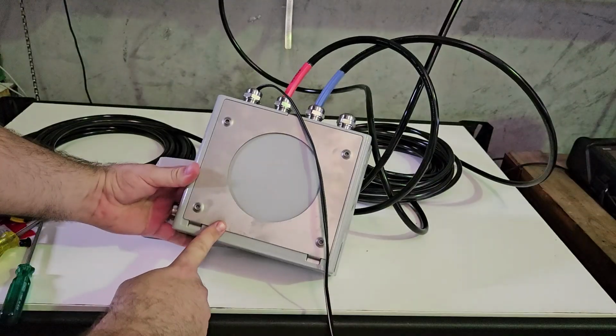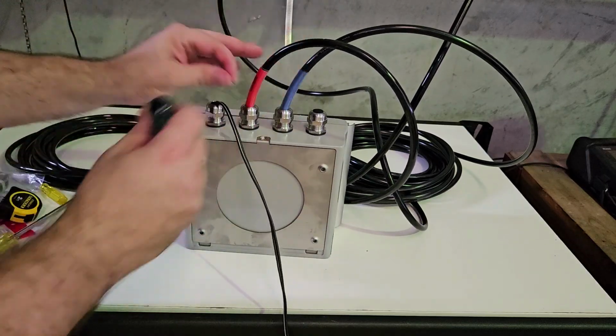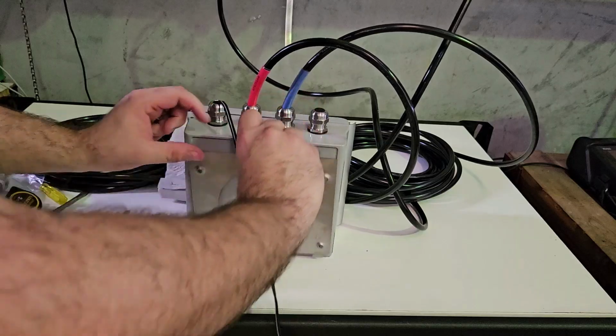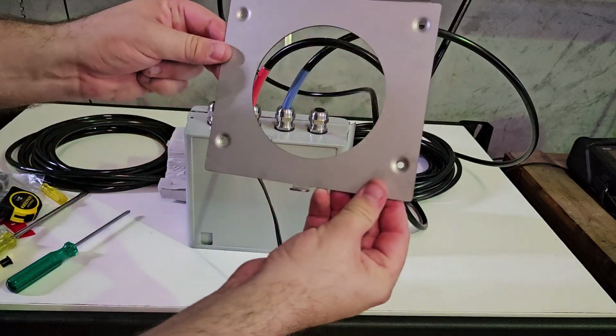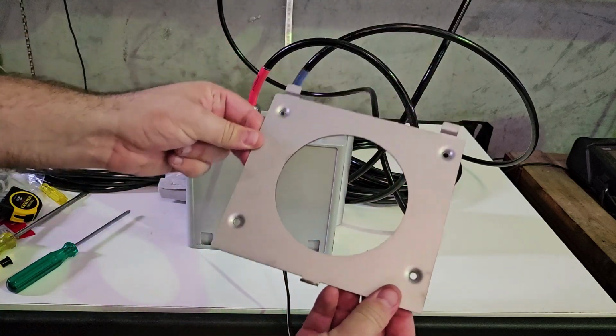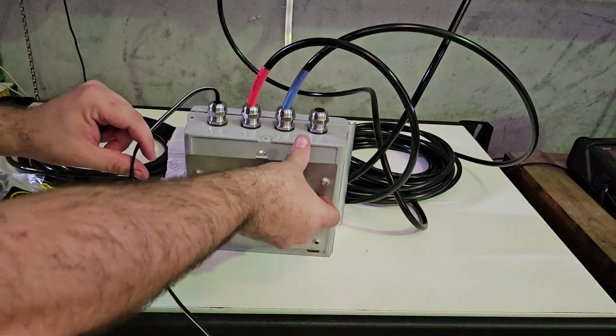The meter has a wall mounting bracket. Just a single screw in the bottom secures it. Remove the screw to loosen the plate. Mount the plate to a wall or post as required, and you can then mount the flow meter back on the plate. That concludes the demonstration.